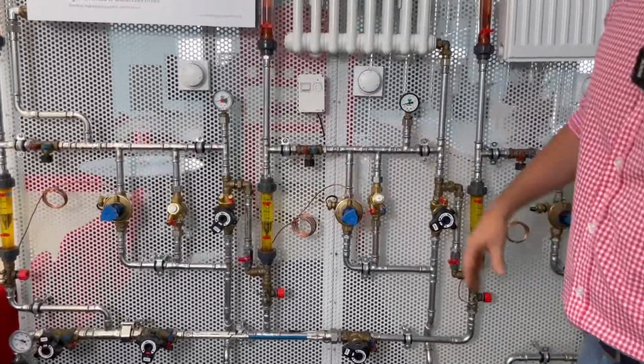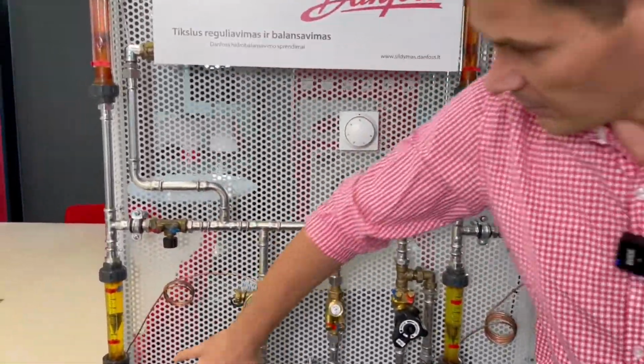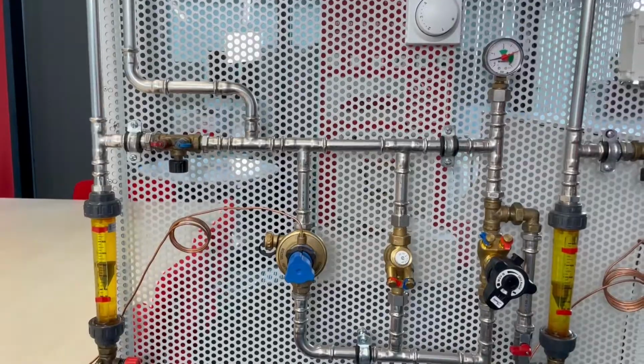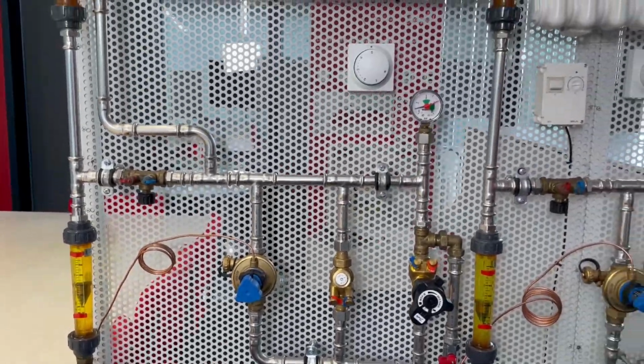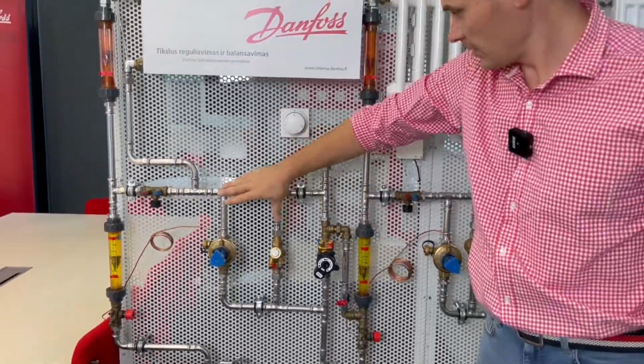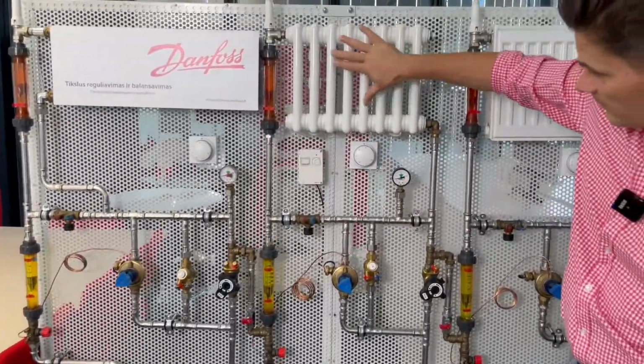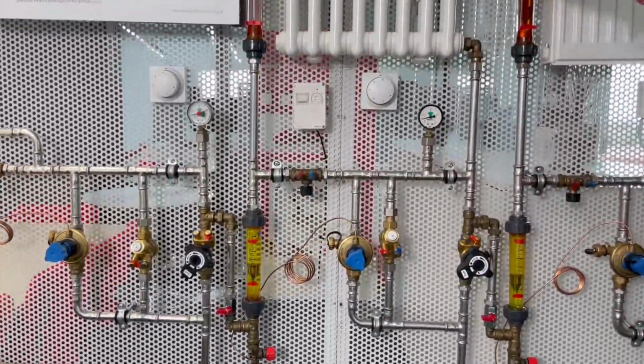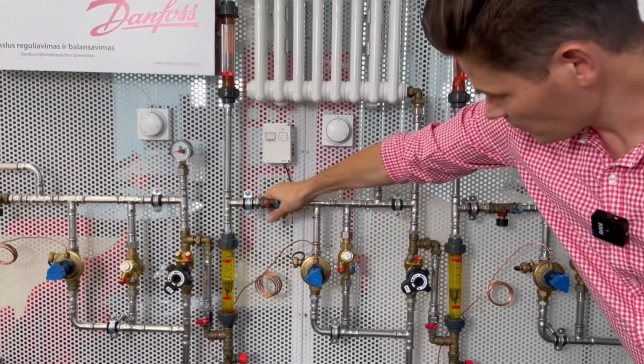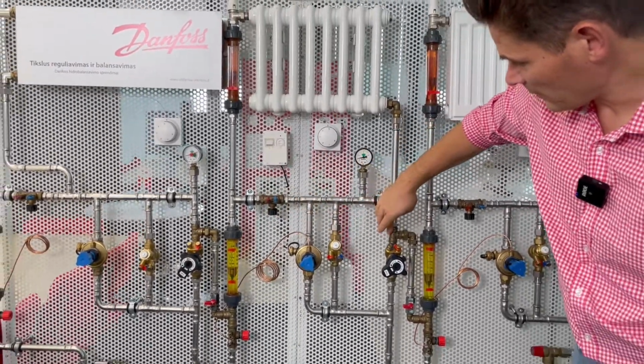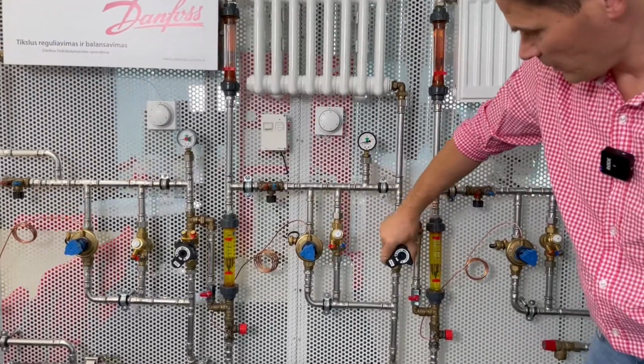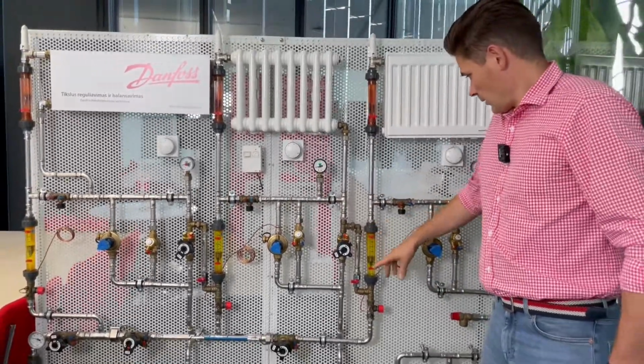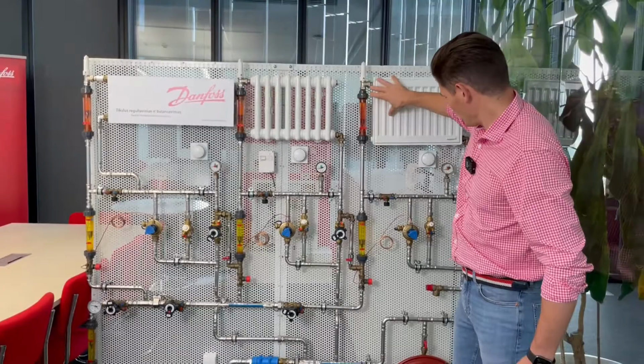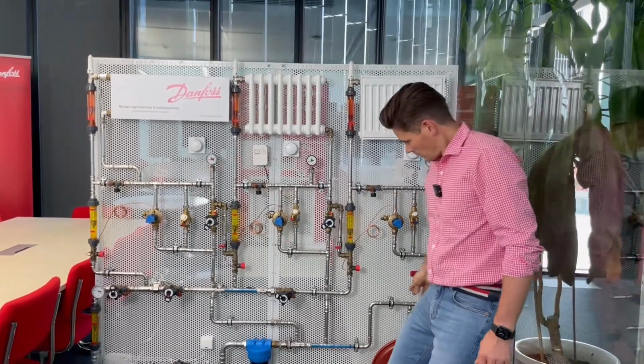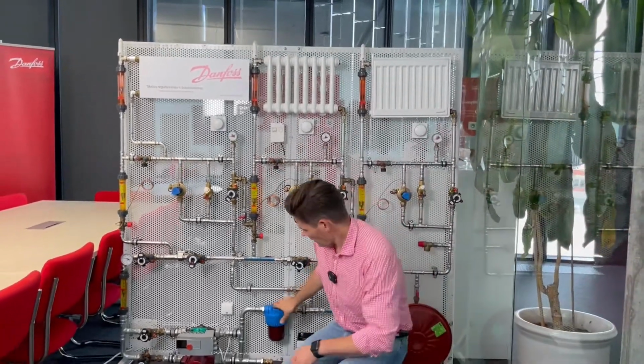It consists of 3 risers. So here is riser number 1. Imagine there are more radiators upstairs. So first riser, second riser, here is the supply line, here is the return line, this one is closed. Here we have 3 types of balancing valves. These 2 are closed and this one is open. The third riser, the last one, is here, return comes here, filter, and it returns to the substation.